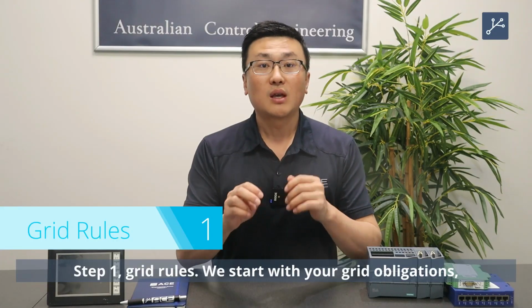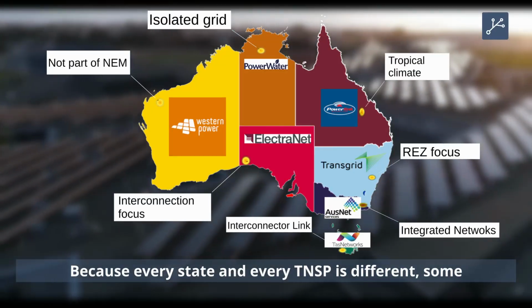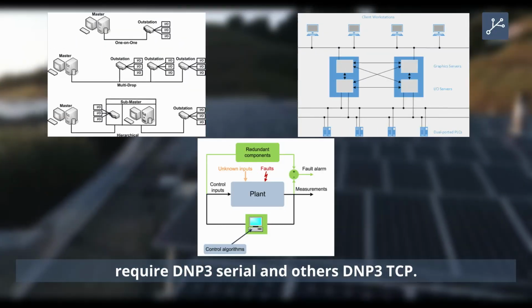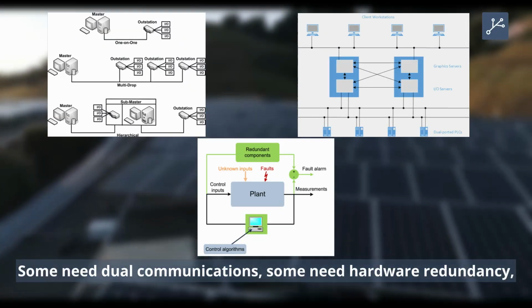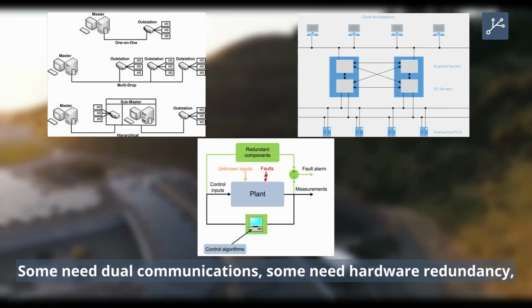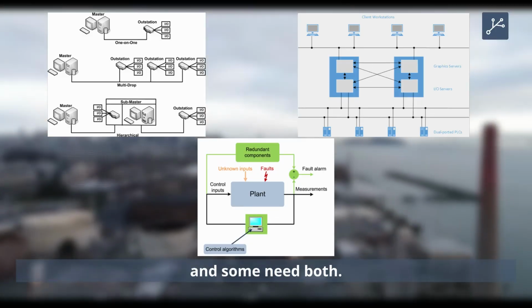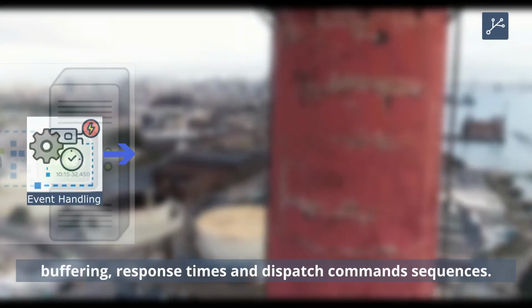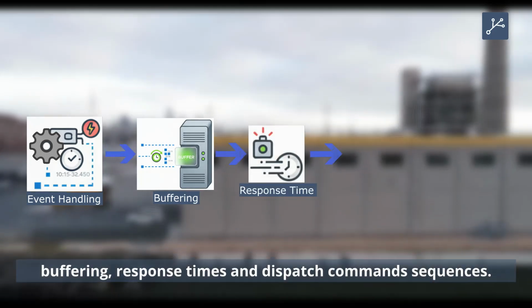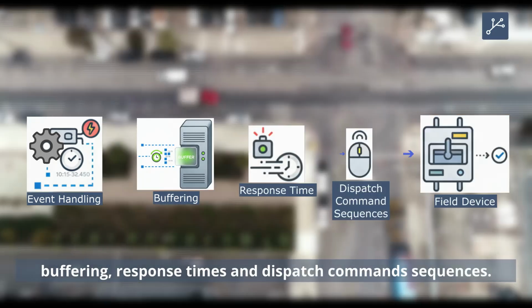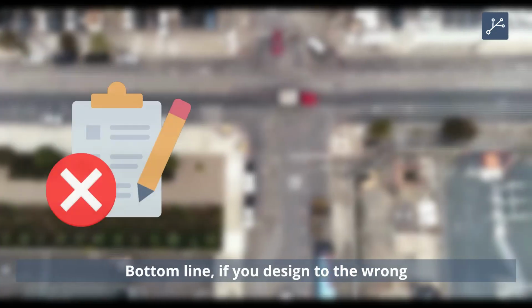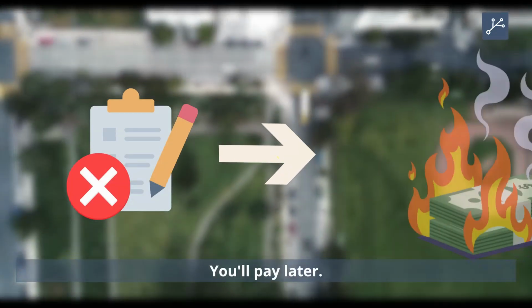Step 1. Grid rules. We start with your grid obligations, AEMO standard, and your TNSP requirements. Because every state and every TNSP is different. Some require DNP3 serial and others DNP3 TCP. Some need dual communications, some need hardware redundancy, and some need both. We also check event handling, buffering, response times, and the dispatch command sequences. Bottom line, if you design to the wrong standard, you'll pay for it later.